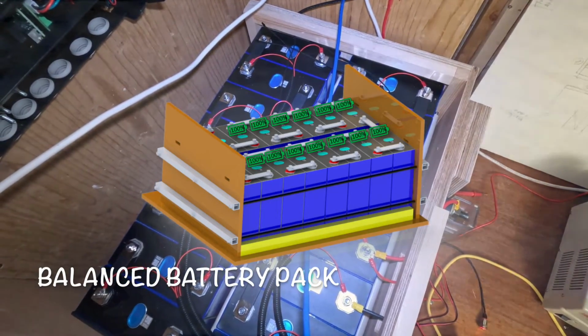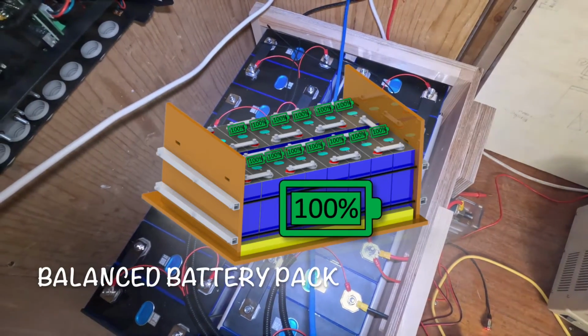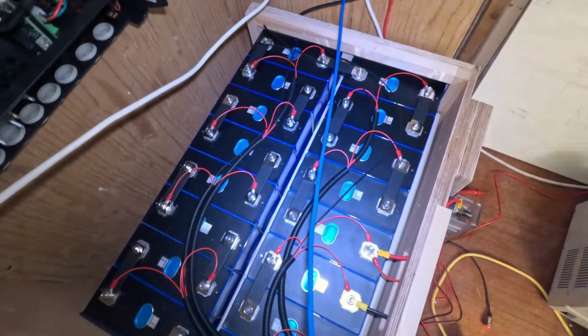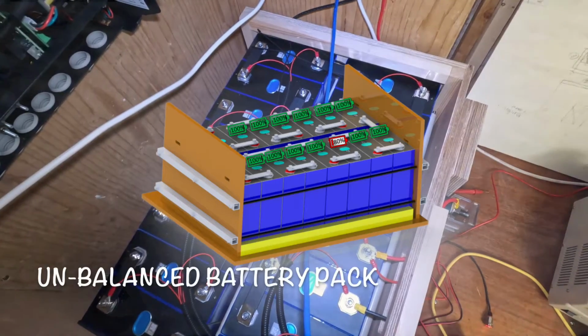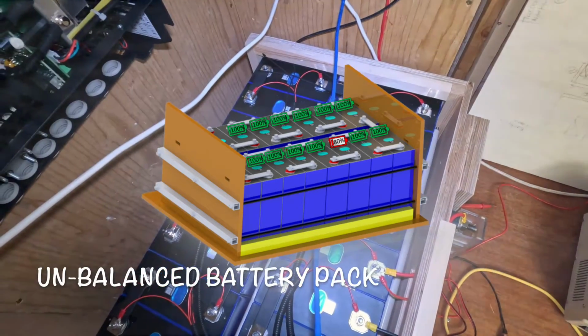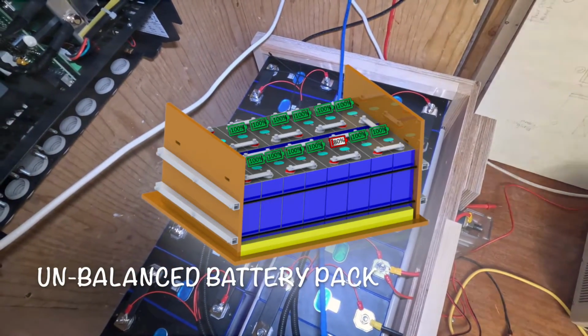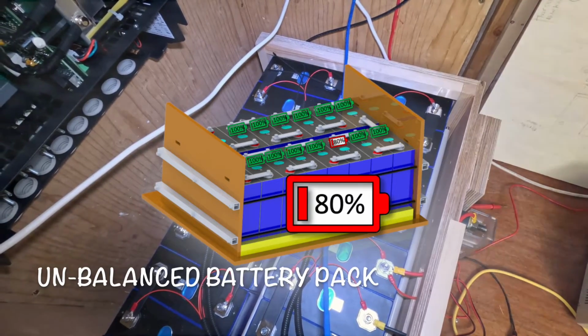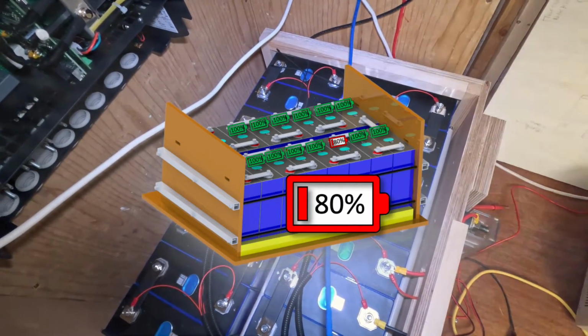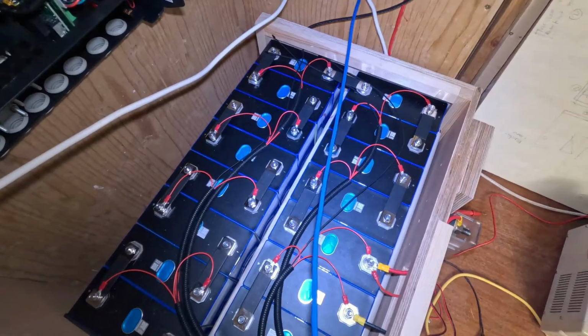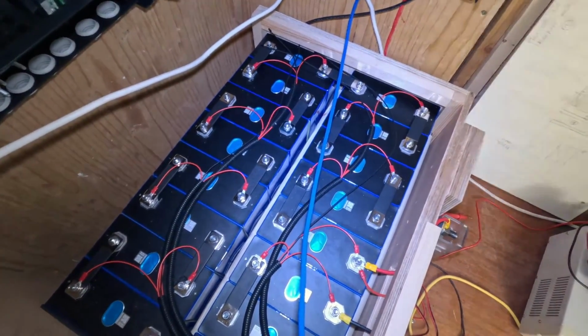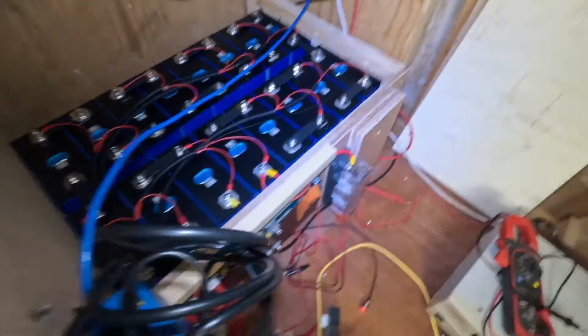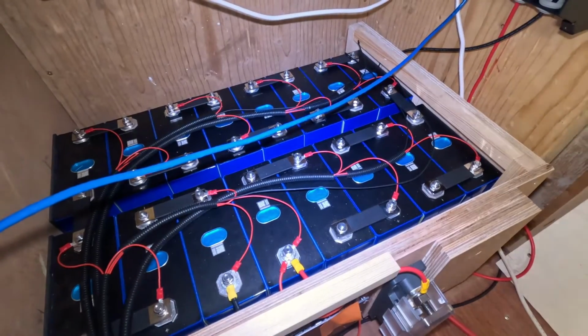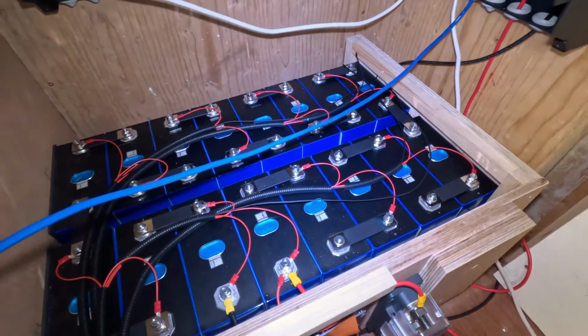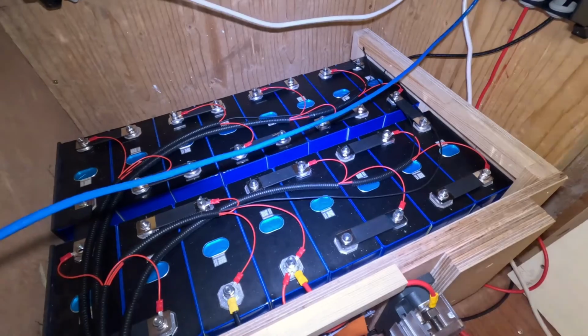Because a setup like this, the whole battery pack together, will not be better than the worst cell, basically. If you just continue like that and never balance anything, the lowest charged cell will never really be fully charged when you charge the battery. And that's basically why you typically have, in an installation like this, some kind of balancing circuit. And in this case, it's integrated in the BMS.